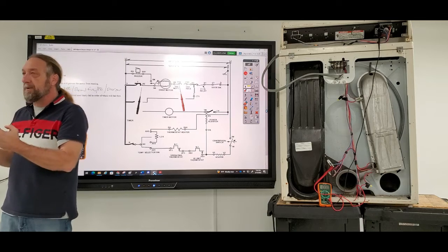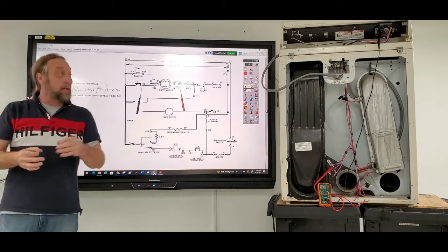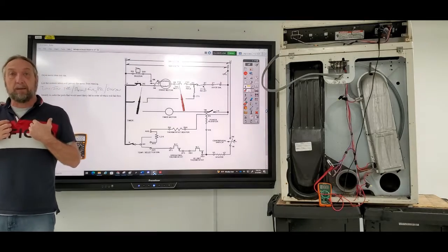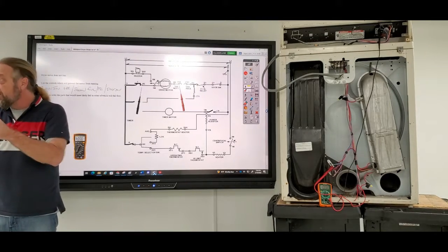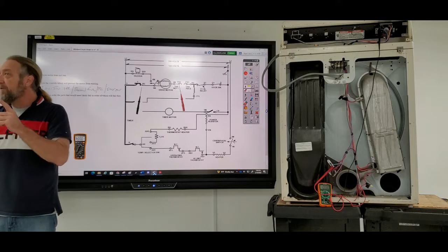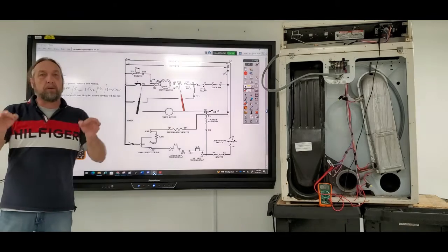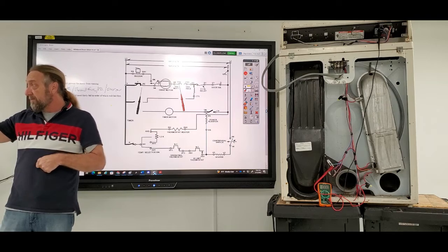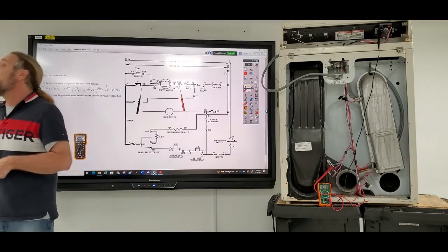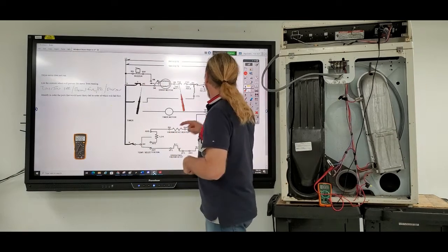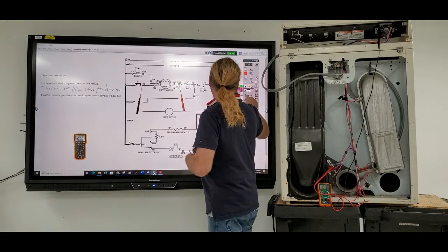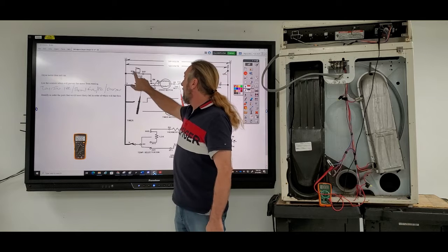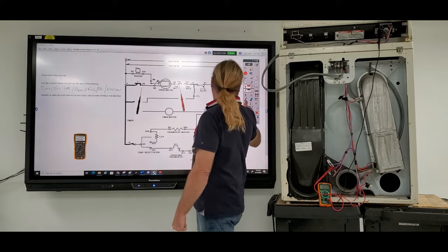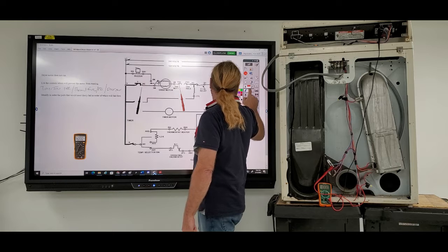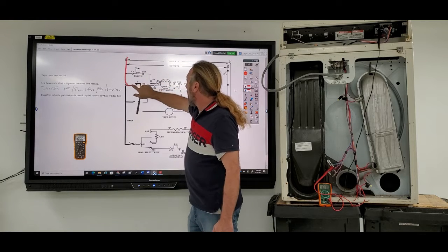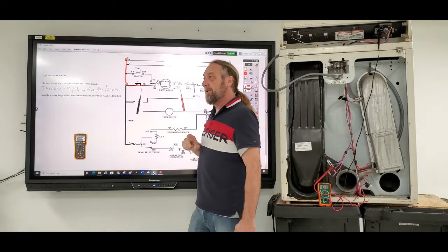And I want you to think about this. What does the voltage at that point mean to me? It means I have voltage to that point. Therefore, if I have voltage to the point, what components in that circuit are good? The ones before the motor. So be specific and tell me what components. The timer switch. Okay, so I'm just gonna use a different color. So the timer switch is good, right? Or at least that part of the timer switch is good. I know that power's up to this point, but what else?